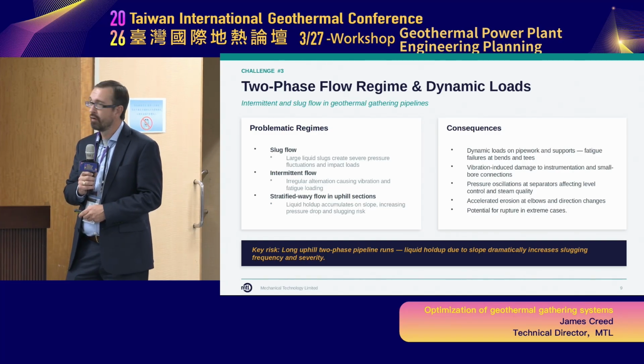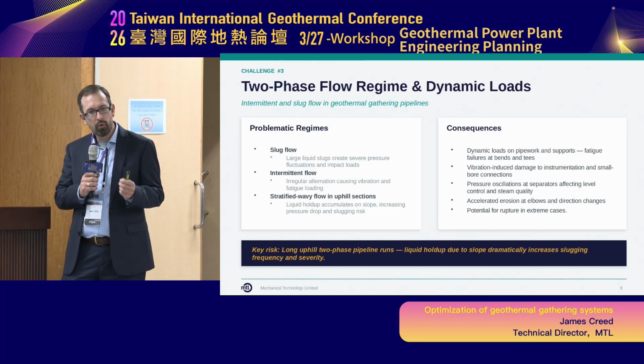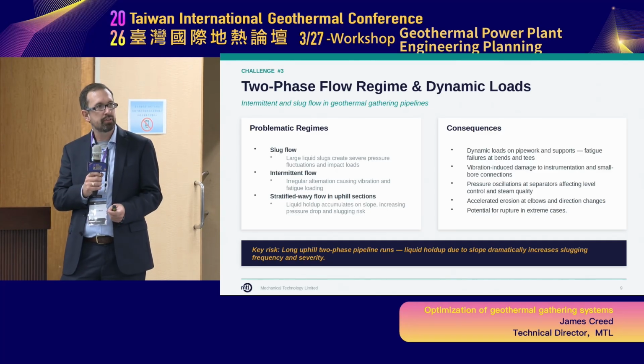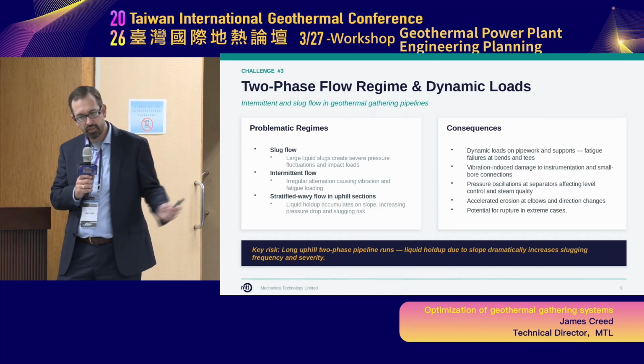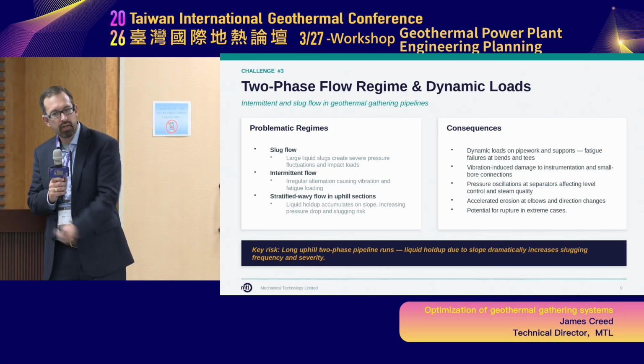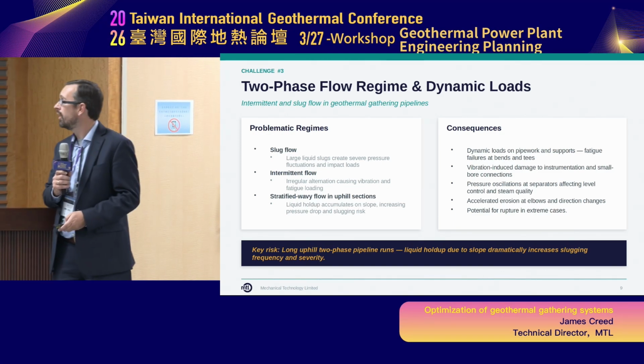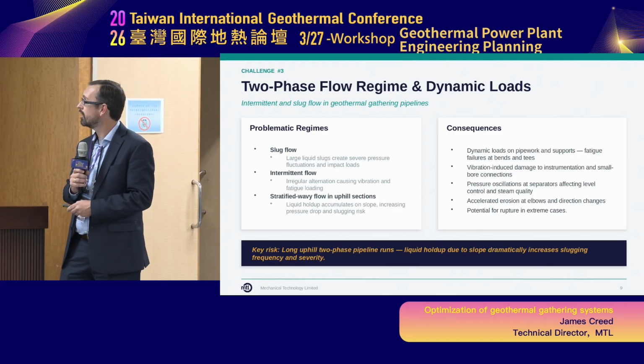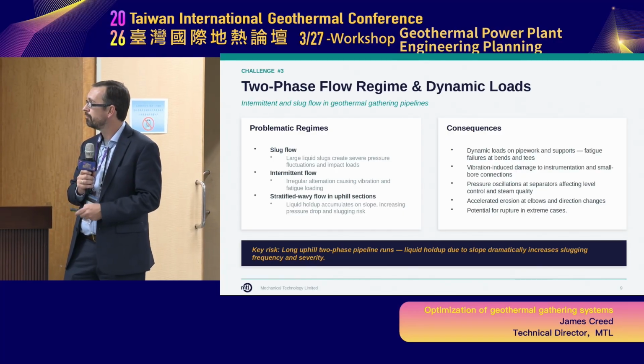Then we get intermittent flow, where you don't get a full slug filling the pipe diameter, but part of the diameter filled with liquid. You see the water rush through the pipe, and get an intermittent loading of water - this causes irregular vibrations and fatigue loading.